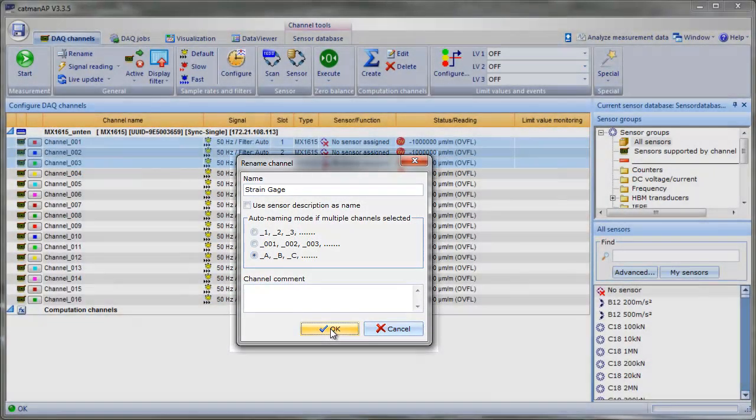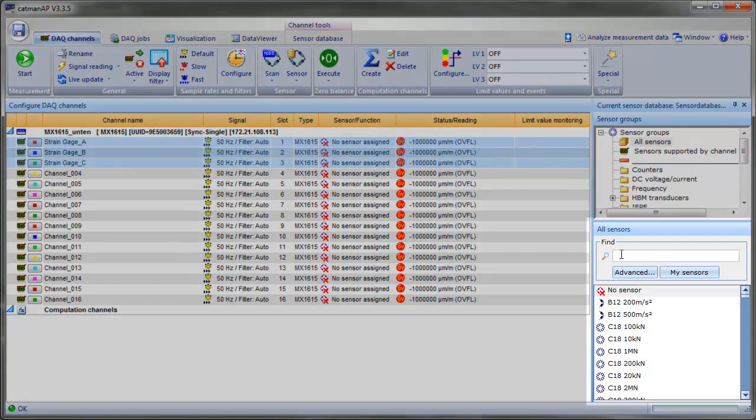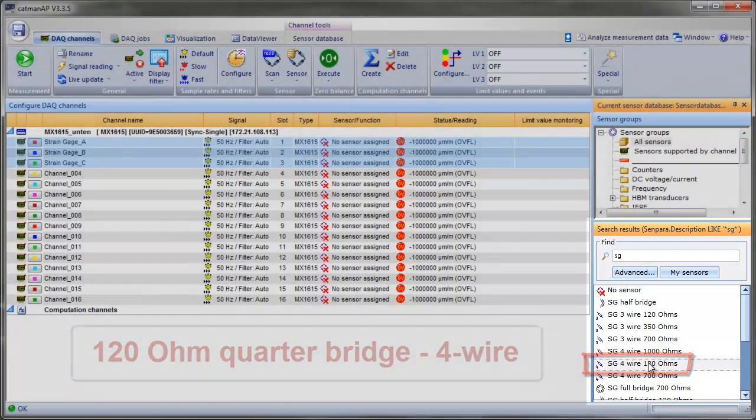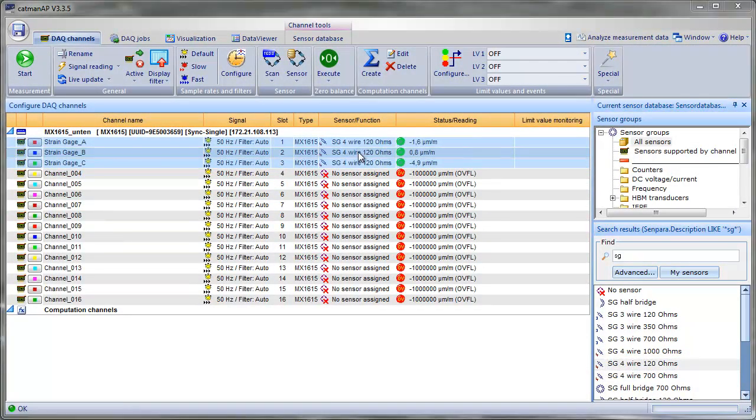Now we have to tell the amplifier what we've connected. We look for the appropriate strain gauge in the sensor database and assign the 120 ohm quarter bridge connected via 4 wire using a simple drag and drop. Immediately, we see values in microstrain and know that we are done with the basic setup.